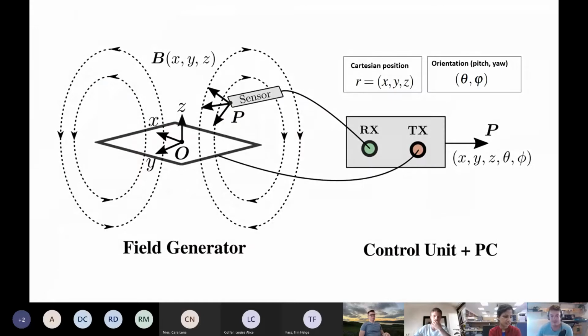So that shows how the whole technology works. In that video we had a few different components: a sensor, which is the small black strip I had in my hand in that little red holder; on the flat piece on the table was the magnetic field generator; and just to the right, a box with a cable, which we call the control unit or base station. The base station sends a current signal to the field generator, which produces a magnetic field, and the sensor detects that field through induction. That signal is sent back to the control unit, where it's measured and turned into a position and orientation.